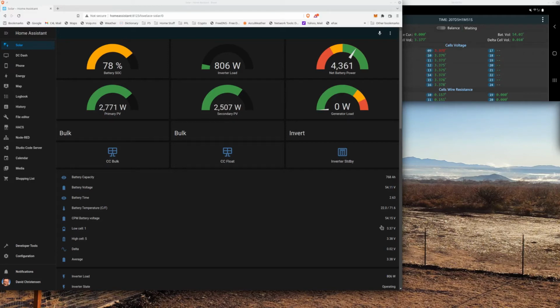So what I can do is flip this to float mode, which stops charging for 30 to 60 seconds, and then the charge controllers will go into float mode. Eventually, because of the draw coming off the system, this delta will come back down.